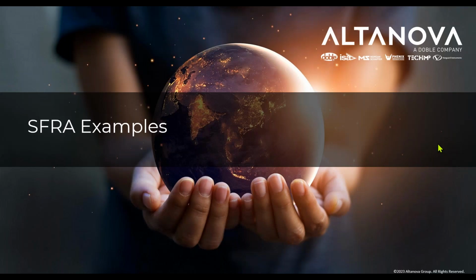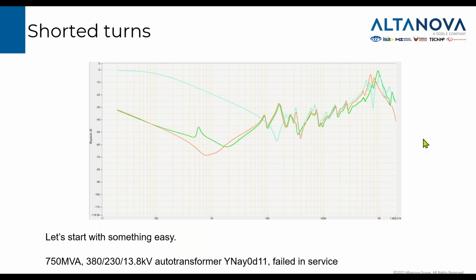Okay, now I would like to present you several examples of successful SFRA measurement on deformed transformers. And I will start from the easiest one. This is just one test made on a transformer, a big 750 MVA auto transformer. It failed in service, and the traces for 3 phases look like here.